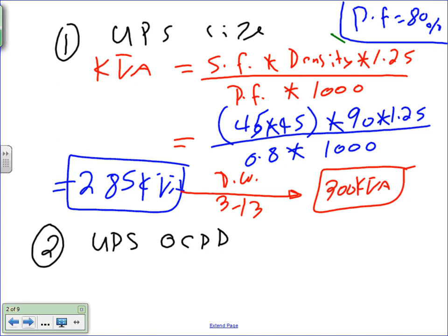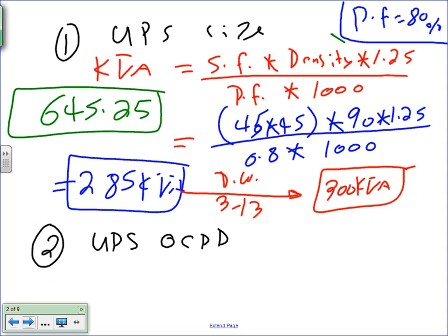Okay, so you can substantiate my opinion here, I'm going to get you an article, 645.25. This is typically where, if you go there, it'll tell you that under engineering supervision you can do anything you want. And that's what we're doing. Under engineering supervision, that's how you calculate it. Okay, 645.25. Okay, let's go to the UPS overcurrent protection device.